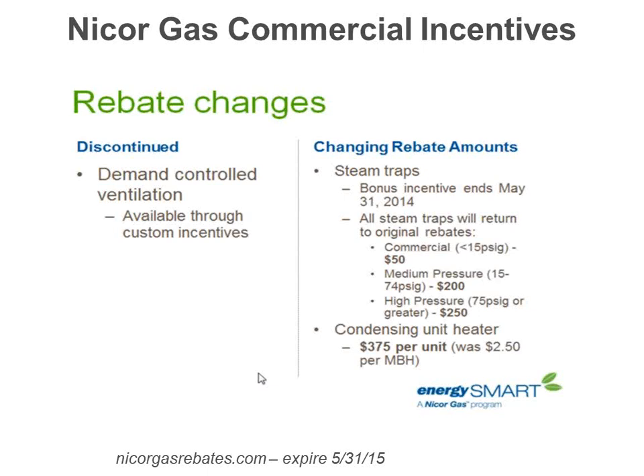It was only on there a year. One of the main reasons why it's off the program is because on a lot of commercial buildings they have VAV systems, which by definition are cooling only. So to get a rebate for DCV, which doesn't really apply during the heating portion, which is morning warm-up, didn't make a lot of sense.